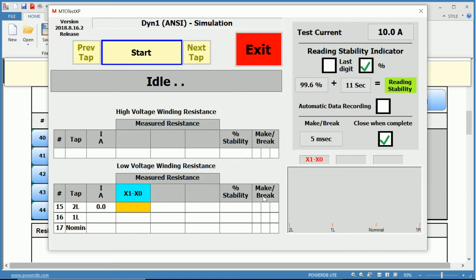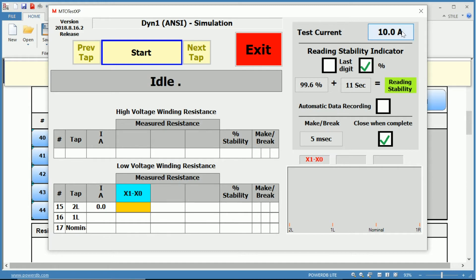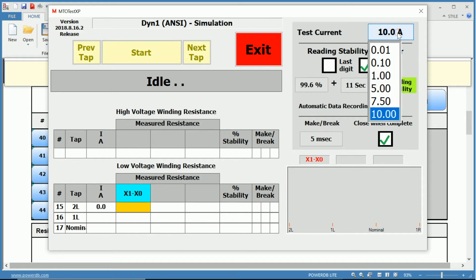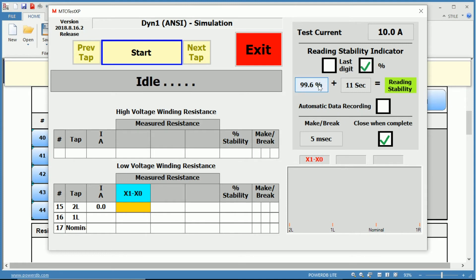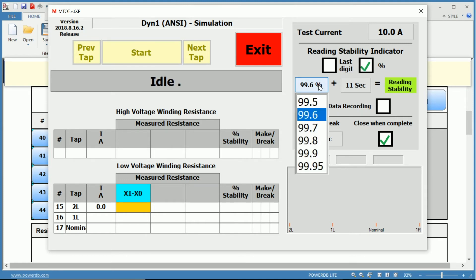So this is our X1 to X0 phase, and then the stability of the current during that measurement, as well as the make-before-break condition, whether it passed or failed. To the right, we have our test settings. We've already saw that we have our test current. We can select between 10 milliamps and 10 amps.